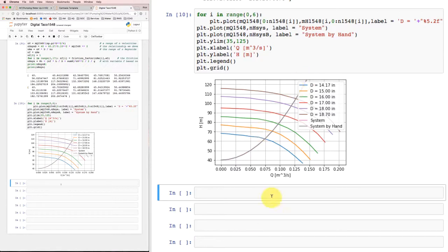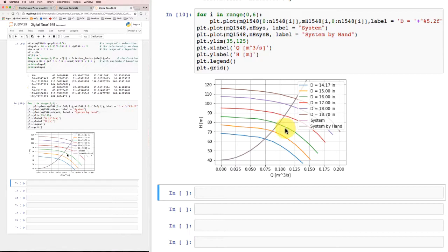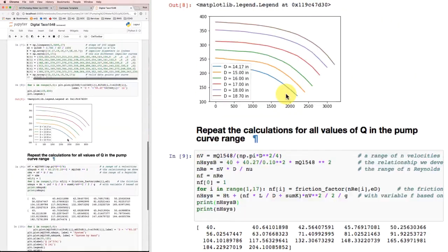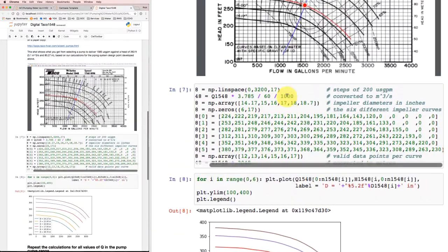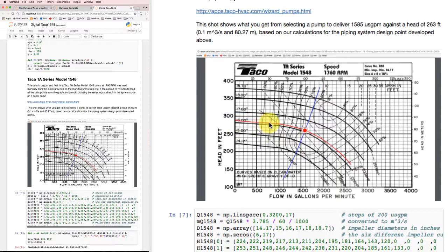But what we do see is that where we had our design flow rate of 0.1 cubic meter per second and our resulting head loss in the pipe of 80.27 meters, that's where we are. And that corresponds to just above this green line. The green line is for the 16-inch impeller. So we're getting the same kind of behavior, the same match for our operating point relative to the 16-inch impeller diameter as we had before.